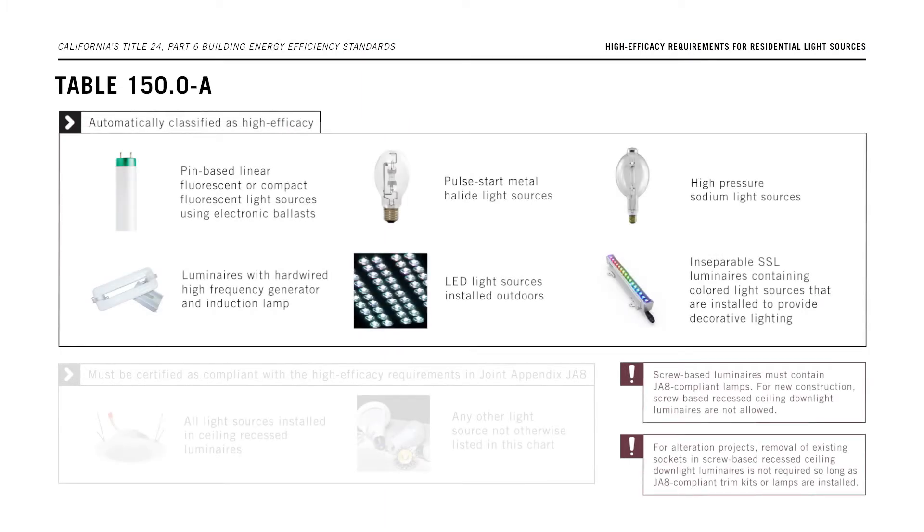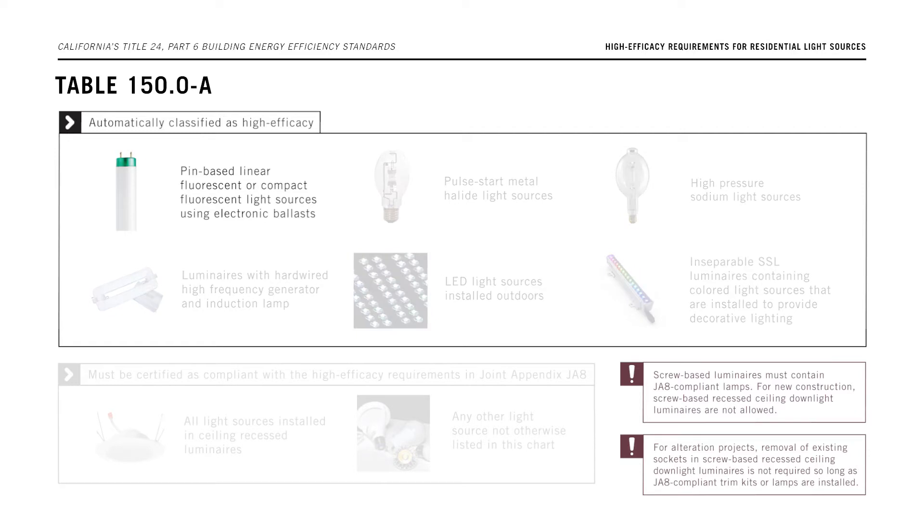Light sources which are automatically classified as high efficacy include Pin-based linear fluorescent or compact fluorescent light sources using electronic ballasts, pulse start metal halide light sources, high pressure sodium light sources, luminaires with hardwired high frequency generator and induction lamps, LED light sources installed outdoors, and inseparable SSL luminaires with colored light sources that are installed to provide decorative lighting.